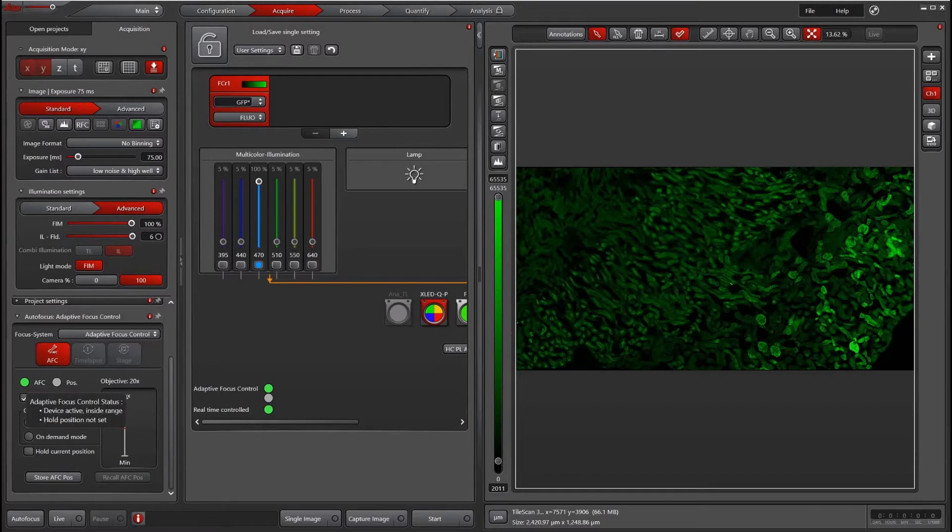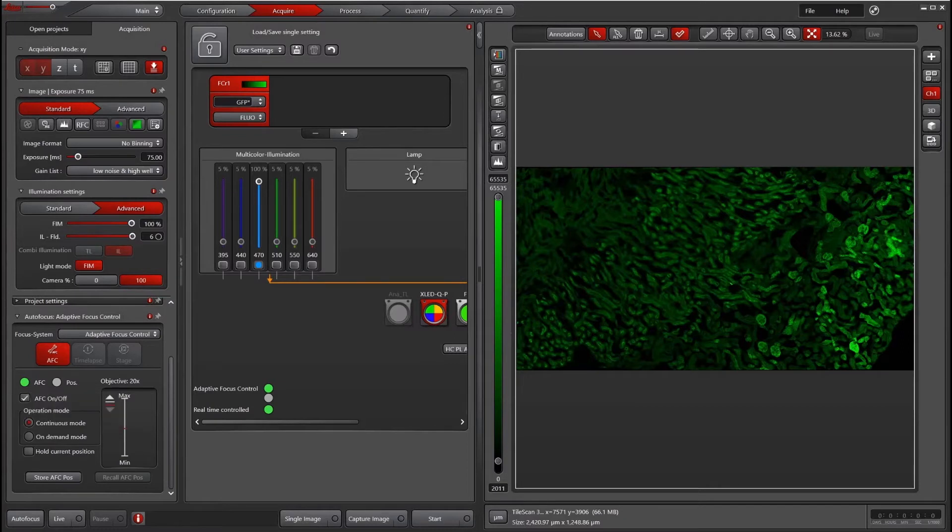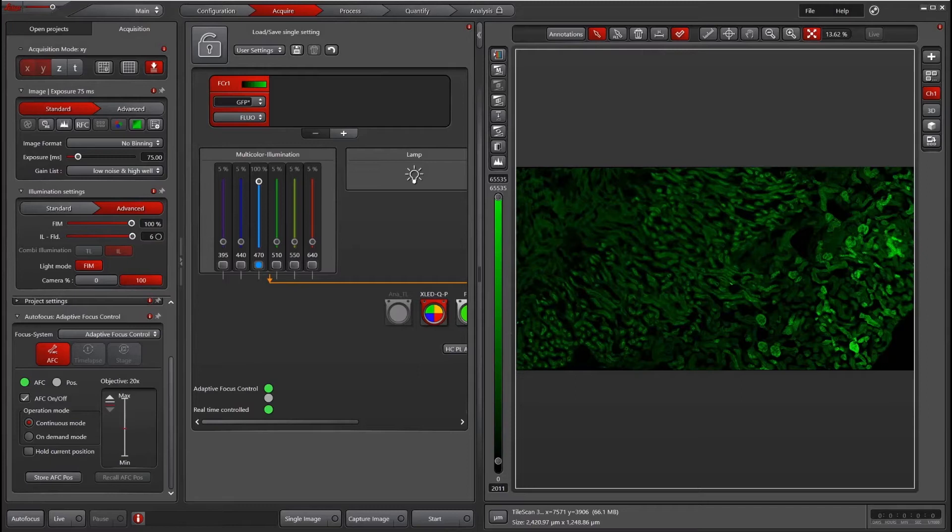The other thing is that AFC will work better when there's a big difference in refractive index. For instance, for a dry objective, the infrared beam is going through air and then hits cover glass or plastic, and that's the interface where there's a big difference in refractive index.